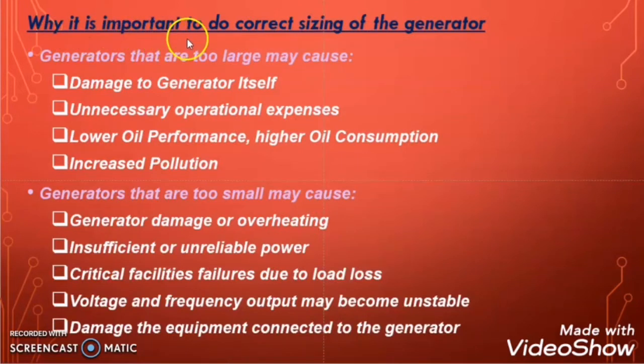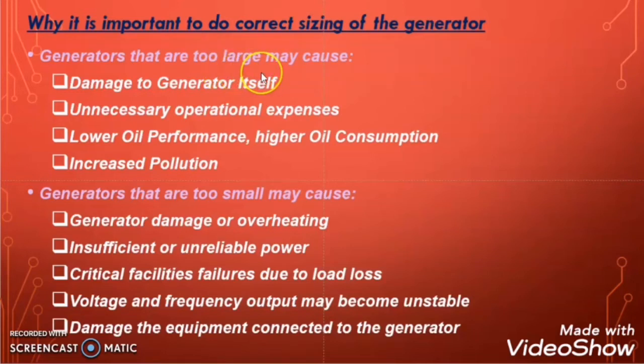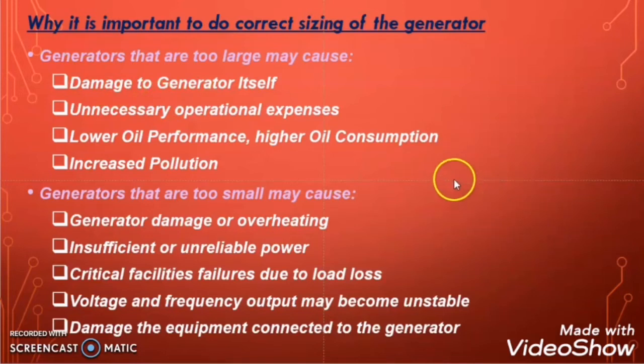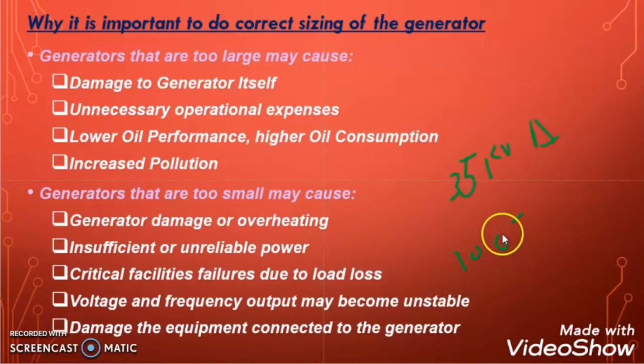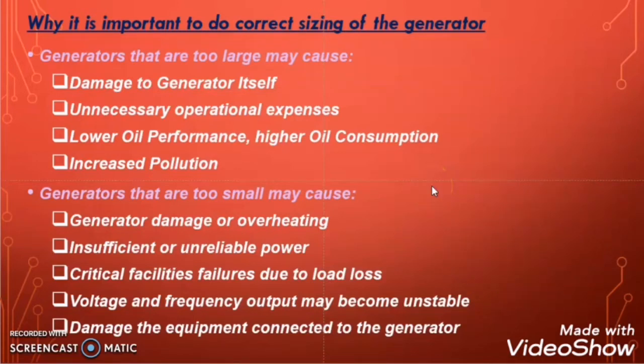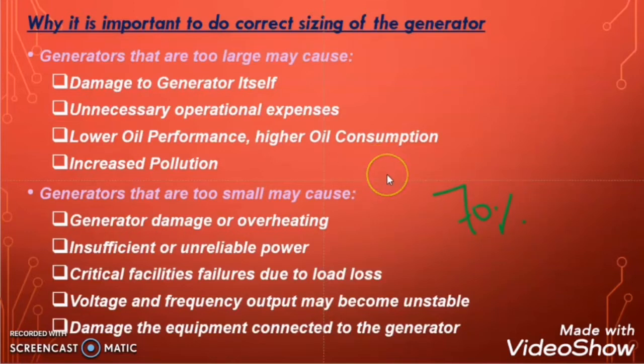Now let us discuss why it is very important to size the diesel generator correctly. Suppose someone sizes a generator which is too large — it means the load processed by the generator is critically lower than the selected rated generator capacity. For example, if you have only 35 kVA load but you selected a genset of 100 kVA, then your genset is called oversized. It is recommended that when the generator is running, the minimum load on the genset must not be less than 70% of its selected rated capacity.